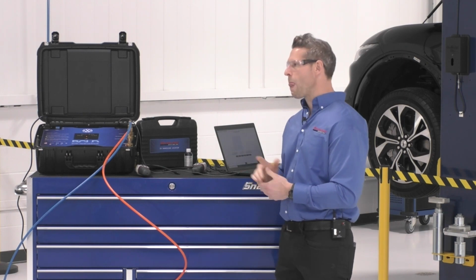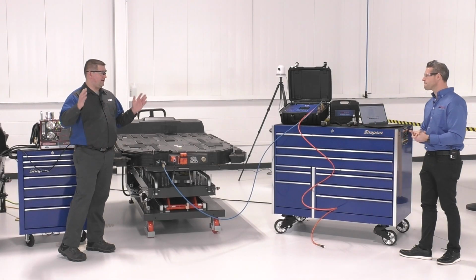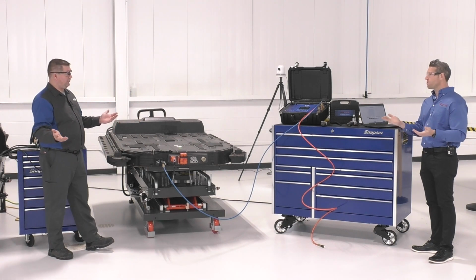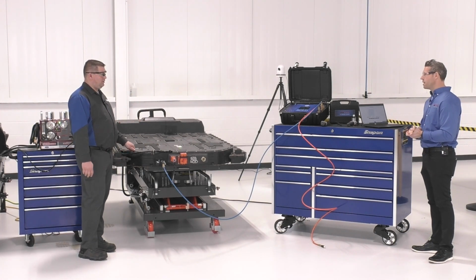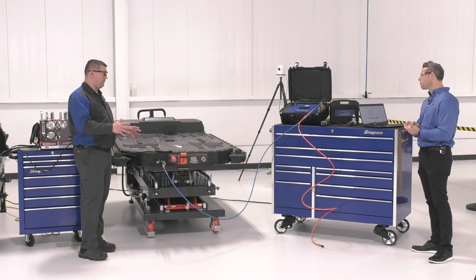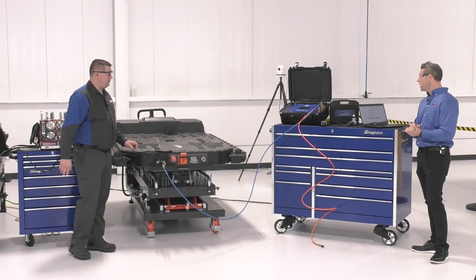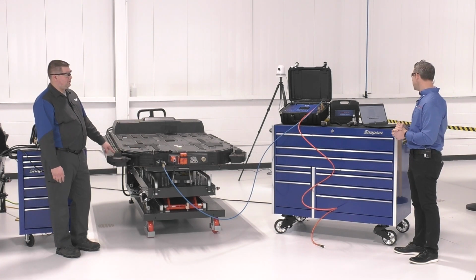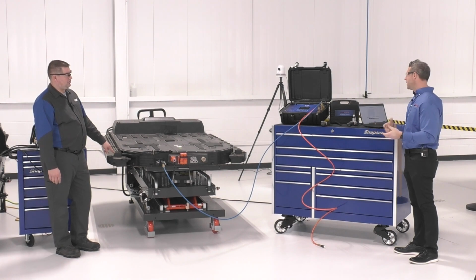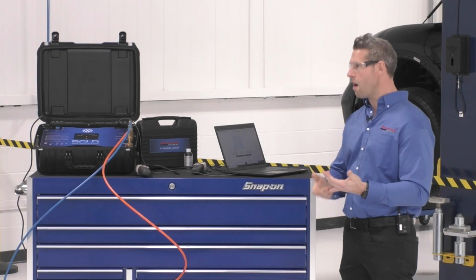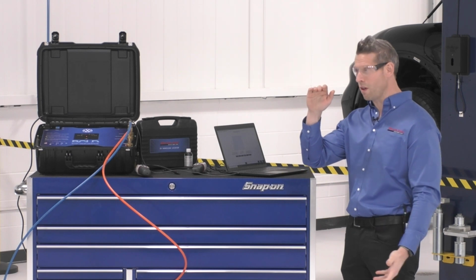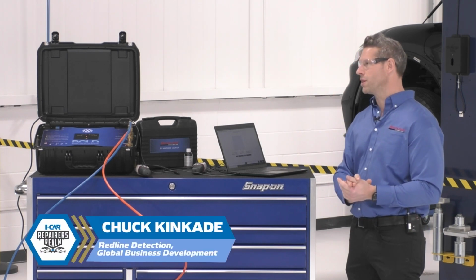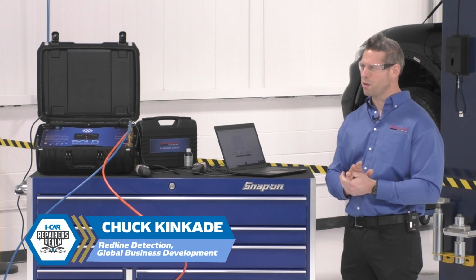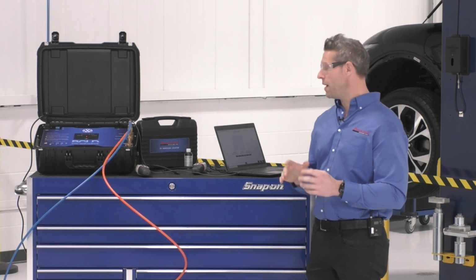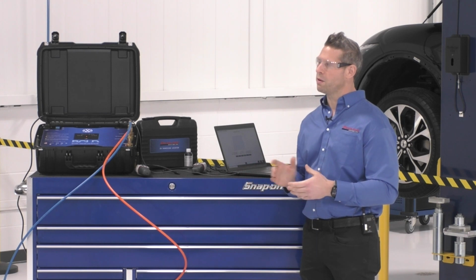So after the stabilization period, it goes into a check procedure, and after that set time, it tells you basically pass or fail at that point. Pass or fail based on a threshold that I came up with that should be pretty close. So this is a nice way to get some good data. What can you do with the data? With this data now, you can get a report. Every test that happens in this equipment is logged, so you get full, high resolution logs of everything that's going on during tests. Usually those logs are really used for engineering purposes more than anything. And then we also get a nice report that we can capture.